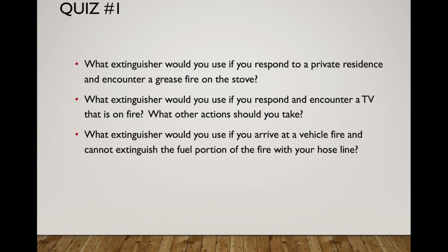If we can, the first thing that we want to do is try and unplug it, or isolate power to it with a breaker, the same that we would do for any other energized electrical equipment fire. We would use our carbon dioxide or BC dry chemical on this. But if we were able to truly isolate power, it has also become a Class A ordinary combustible fire and would be appropriate for water use.